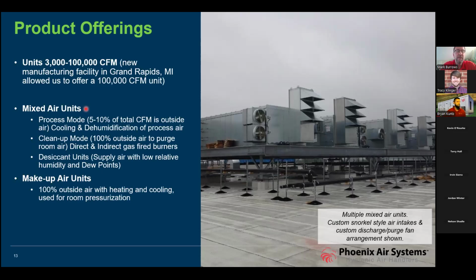They're very different. The process mode, or I call the money shot, that's where the end user is producing whatever he's producing. We take 5 to 10% of the total CFM, and that's used for positive pressure in that room. We don't want to see any doorways being sucked in the process room. We want to make sure we have a slight positive pressure so this good, clean, cooled air is going out in the hallway, not letting any of that bad air in.